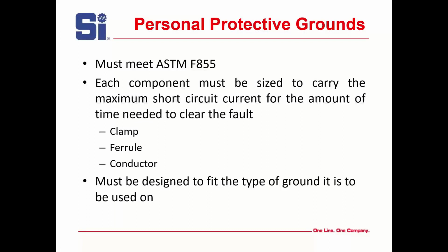Personal protective grounds, on the other hand, must meet the requirements of ASTM F855. Each component must be sized to carry the maximum short circuit current for the amount of time needed to clear the fault. And again, that's everything. It must be designed, and this is important, a lot of people miss out on this. The ground clamp has to be designed to fit the type of ground it's going to be. Is it round? Is it flat? You have different types of ground clamps designed for different types of grounds.